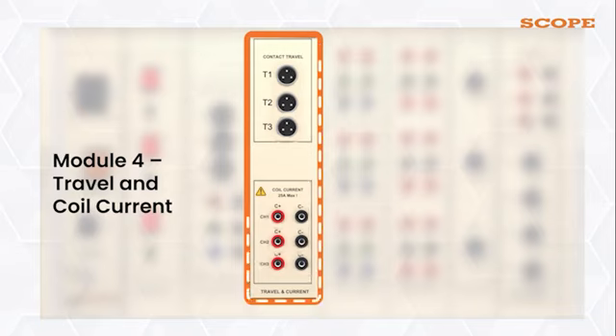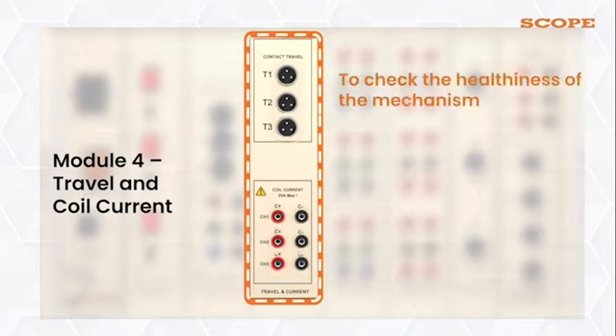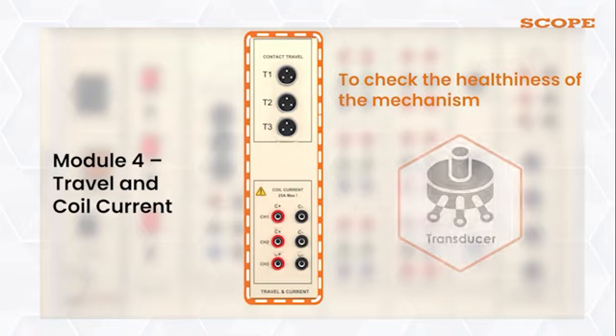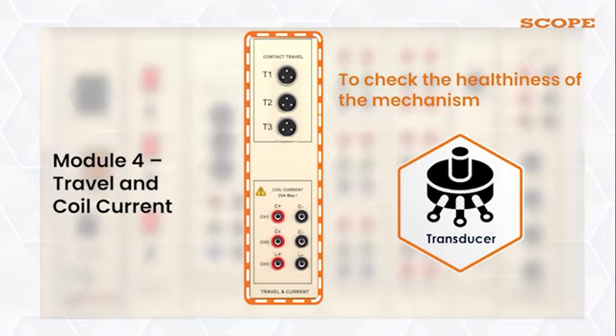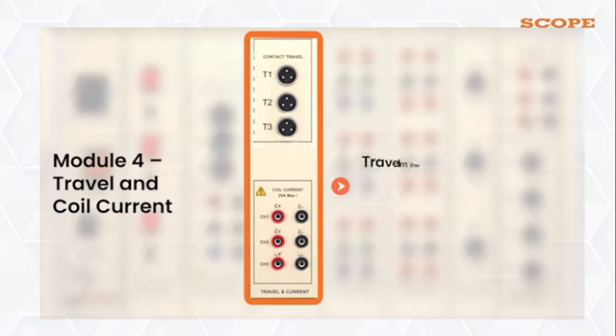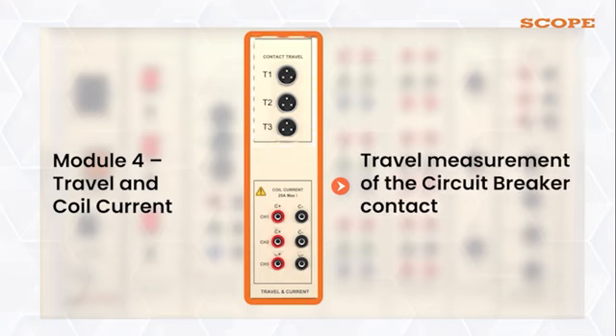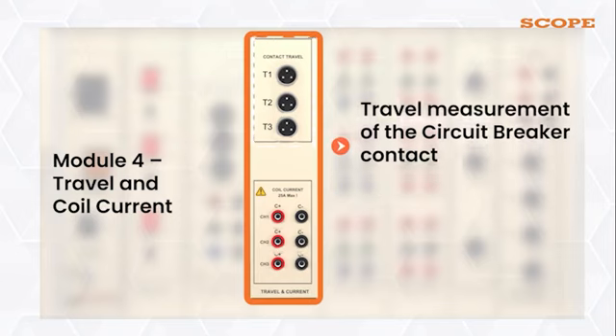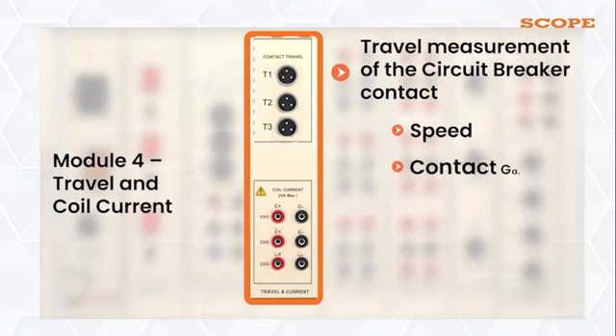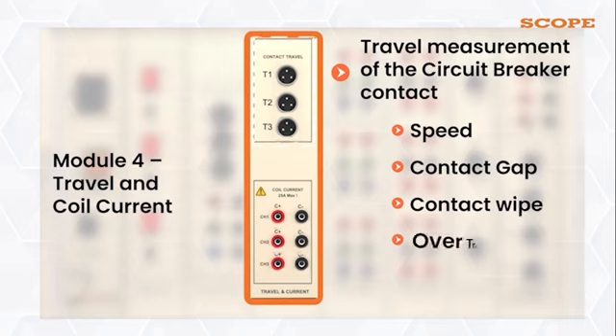Module 4. Travel and Coil Current Module. To check the healthiness of the mechanism, a travel channel is used. For this, transducer is connected to the mechanism of the circuit breaker. The travel measurement of the circuit breaker contact is very essential as it helps you to understand various parameters like speed, contact gap, contact wipe, over travel, rebounds, etc.